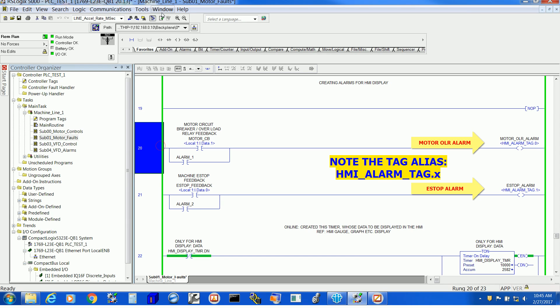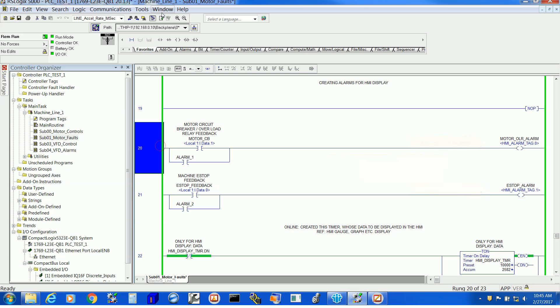You can see Motor Overload Alarm and E-Stop Alarm — those tags are made alias to our alarm tag, that is HMI Alarm Tag dot 0 and dot 1. It can go all the way to dot 31 being a double integer. We can definitely create more than one double integer alarm tag, so our alarm limitations are not just 0 to 31; we can create multiple tags.